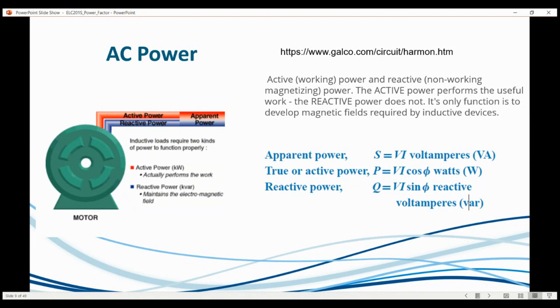If you're running a motor, which is typically inductive due to electromagnetic induction and conductors crossing a magnetic field, the active power component is what actually performs the work, driving the shaft. If that's coupled to a pump or compressor, we only get the kilowatt from the active power, the red part in this diagram.